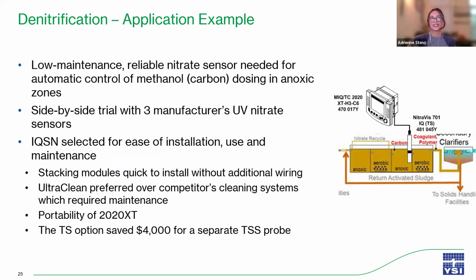So this is an application example of an optical nitrate sensor, which was used to control carbon dosing in an anoxic zone at a plant. There was a side-by-side trial of 3 manufacturers' UV nitrate sensors. And in the end, YSI IQ SensorNet was selected due to the ease of installation, ease of use, and ease of maintenance. Particularly, they liked our modules, which can be stack mounted up to 3 modules per stack, which reduces the need for additional cabling between modules.